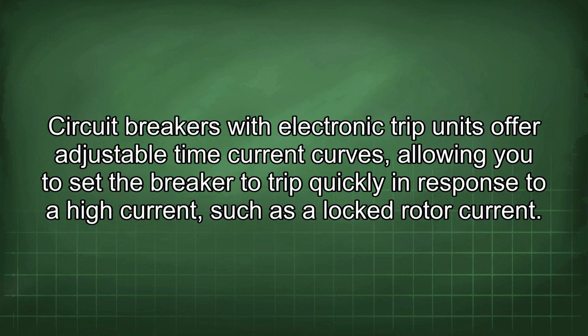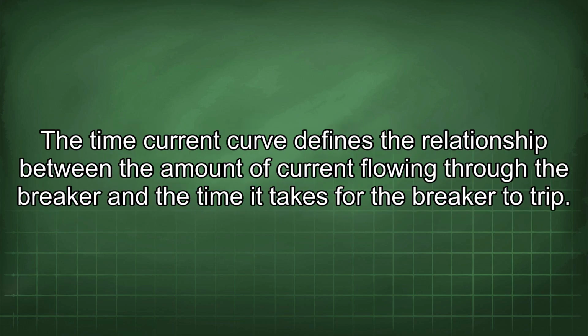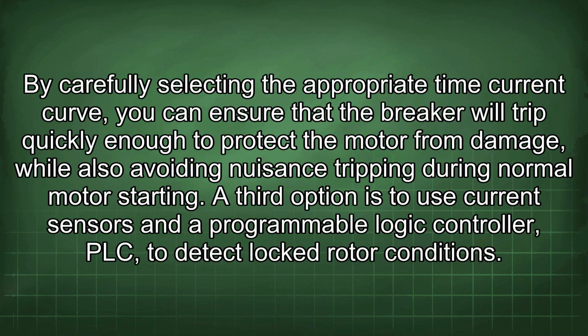Circuit breakers with electronic trip units offer adjustable time current curves, allowing you to set the breaker to trip quickly in response to a high current, such as a locked rotor current. The time current curve defines the relationship between the amount of current flowing through the breaker and the time it takes for the breaker to trip. By carefully selecting the appropriate time current curve, you can ensure that the breaker will trip quickly enough to protect the motor from damage, while also avoiding nuisance tripping during normal motor starting.